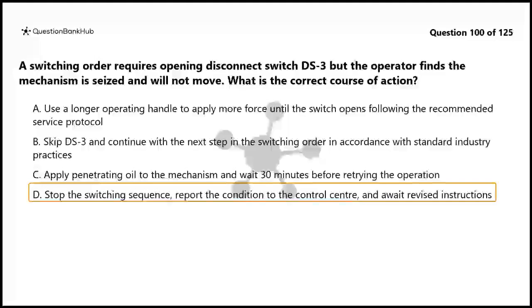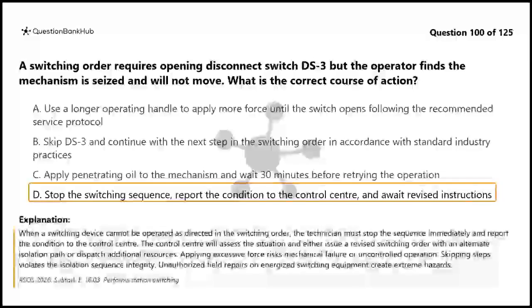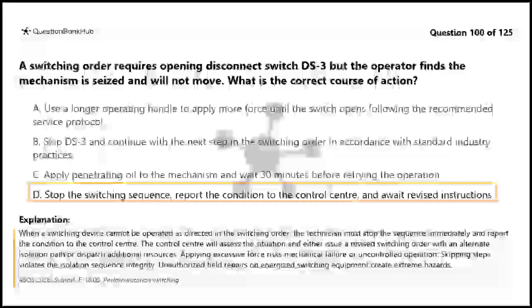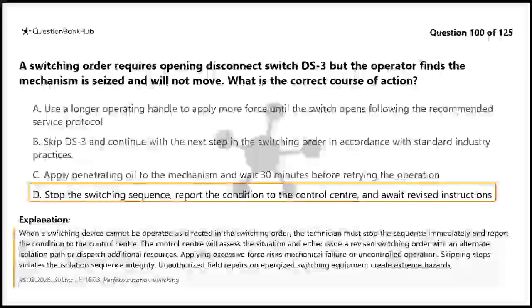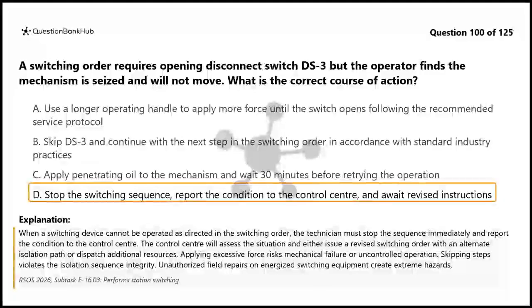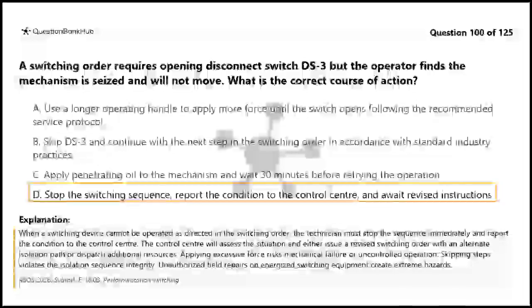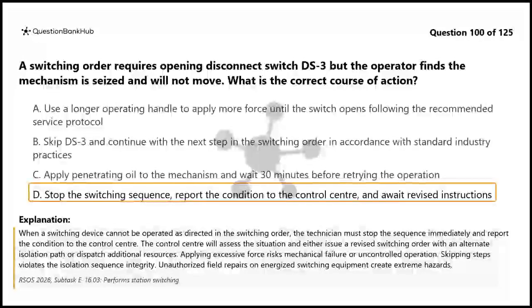The correct answer is D. When a switching device cannot be operated as directed in the switching order, the technician must stop the sequence immediately and report the condition to the control center. The control center will assess the situation and either issue a revised switching order with an alternate isolation path or dispatch additional resources. Applying excessive force risks mechanical failure or uncontrolled operation. Skipping steps violates the isolation sequence integrity. Unauthorized field repairs on energized switching equipment create extreme hazards.